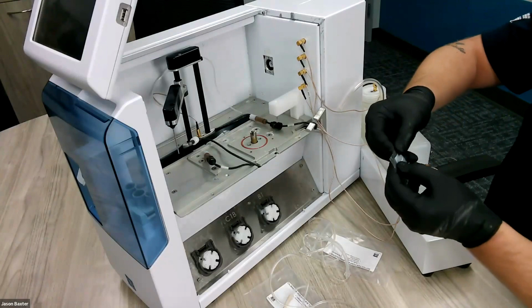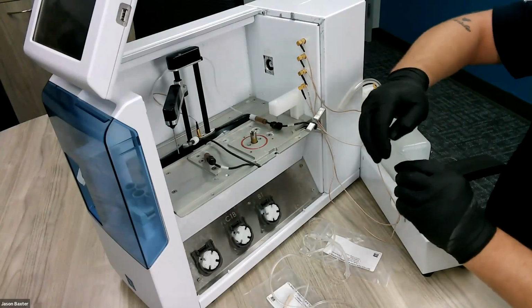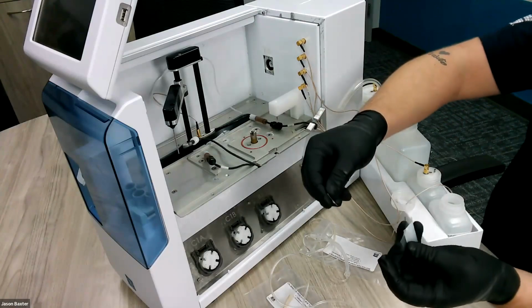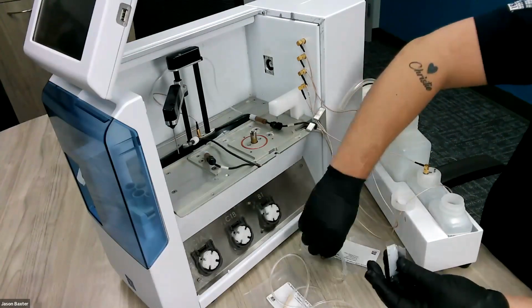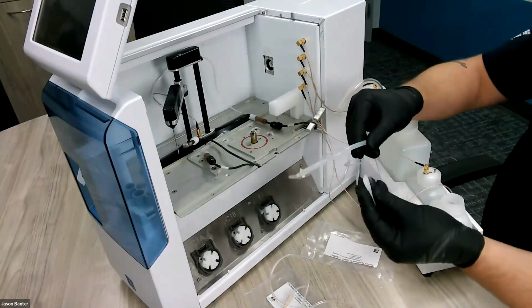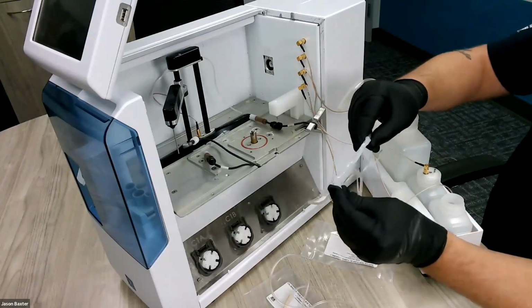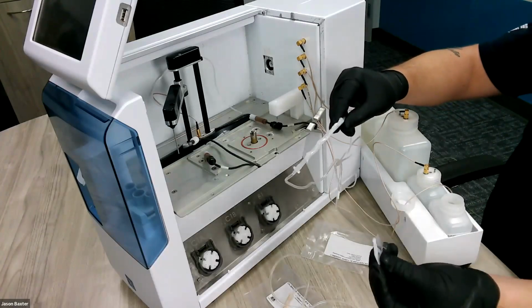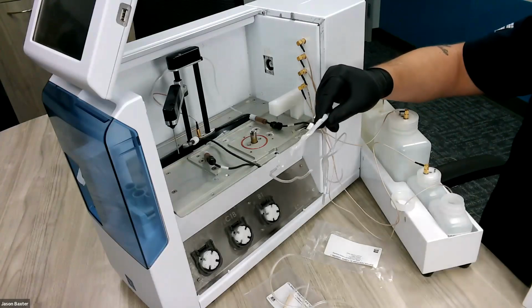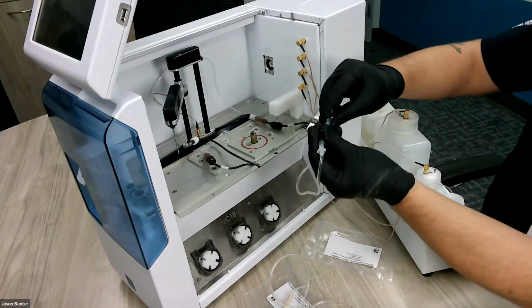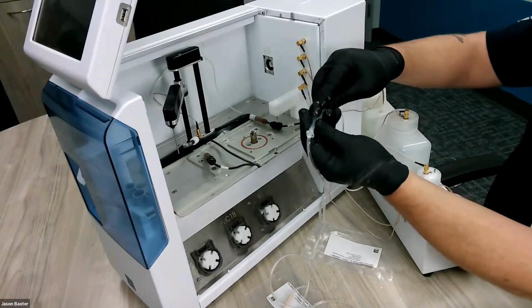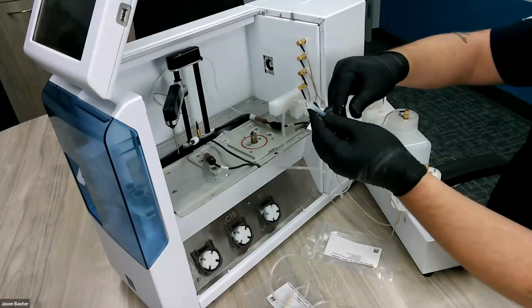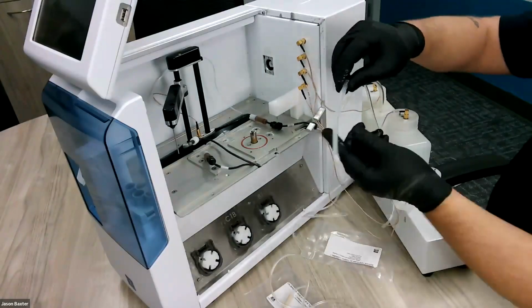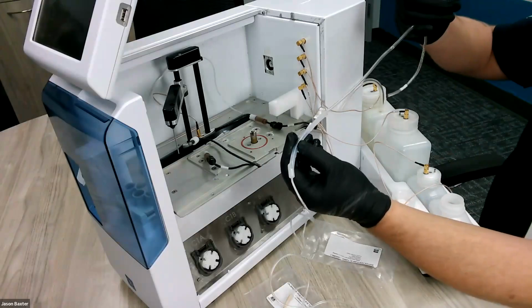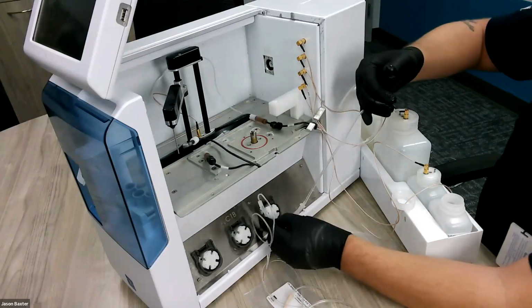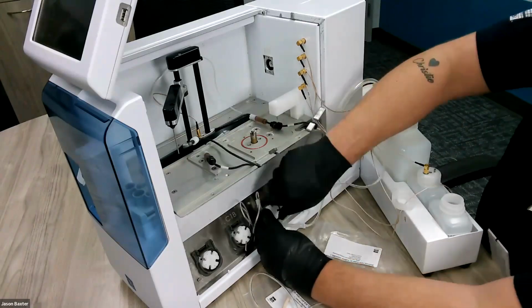So this is where you really need to wear gloves, or if you have some kind of cutting device or a pair of scissors, that's great. Otherwise, you can just tear open the end of the blister pack. Take a small amount of this grease. Actually, for the buffer pump, you use about half of a packet. Set this grease to the side. It's going to come in handy later. You're going to want to smother and smear this grease all around in this tubing. So you definitely want to wear gloves. Otherwise, you're going to leave your fingerprints everywhere for the next day. So you'll remember the inlet side is on the right-hand side. So what I will do is I will start by putting this into the peristaltic pump.